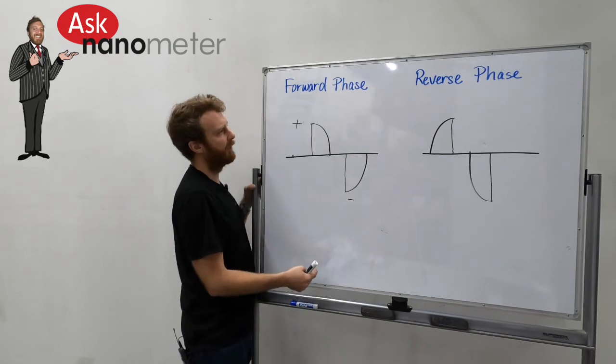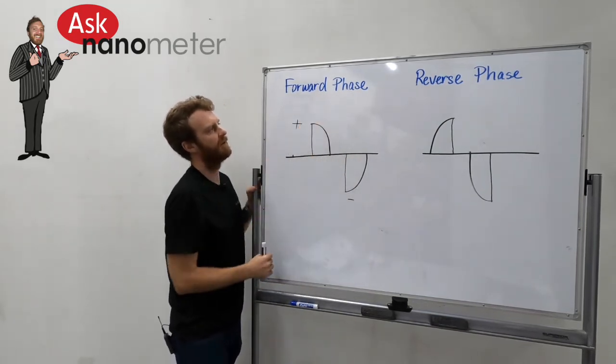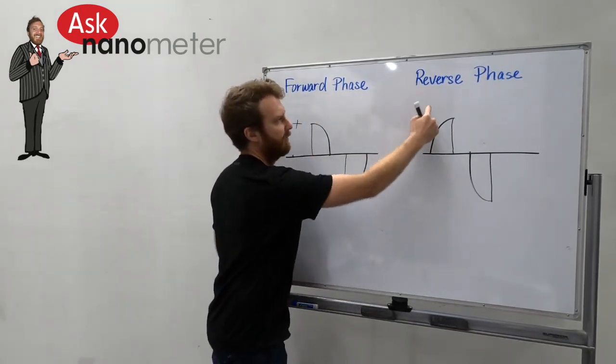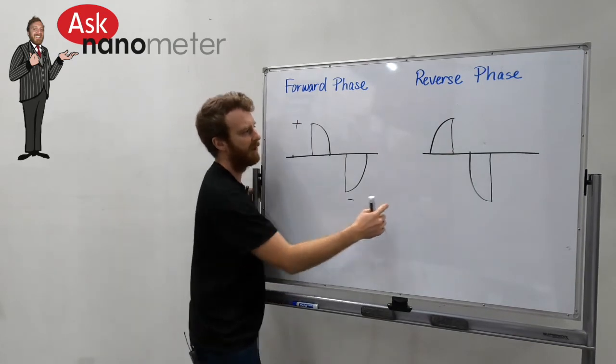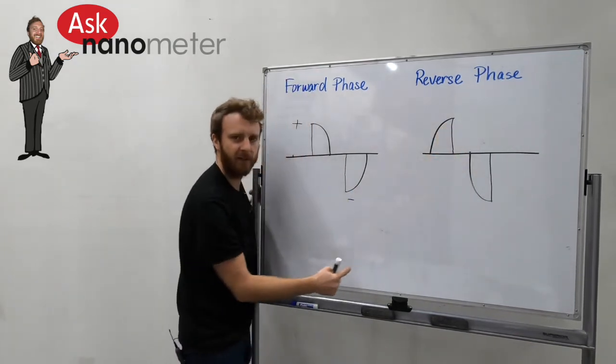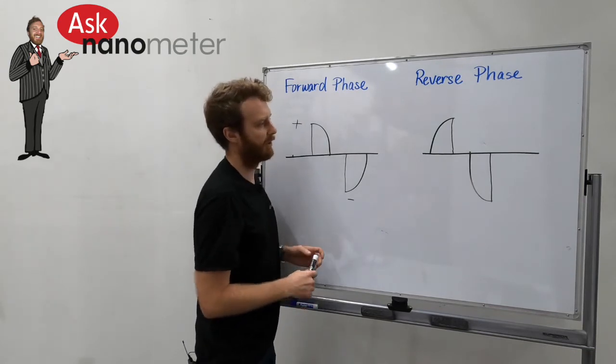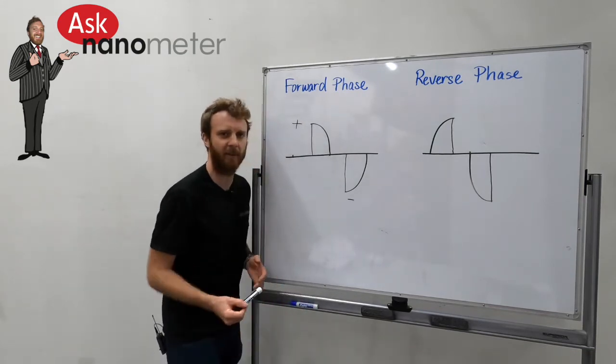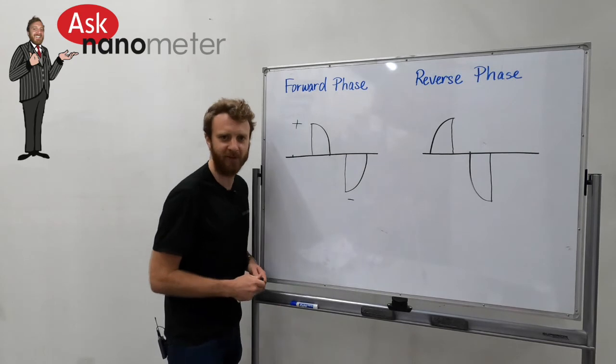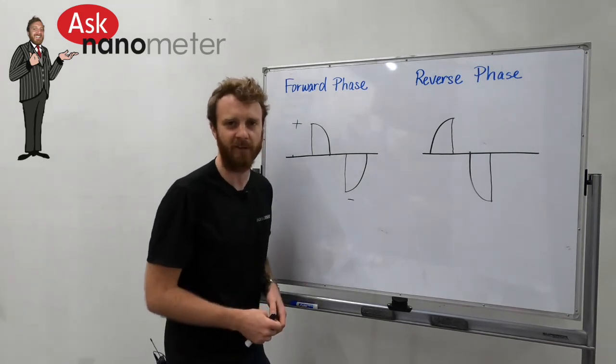On the flip side, if we were to take a forward phase driver and attach it to a reverse phase dimmer, because we're interrupting the power on the trailing edge, you're going to end up getting large kickback voltages on the load side and ultimately over time it's going to blow it up.